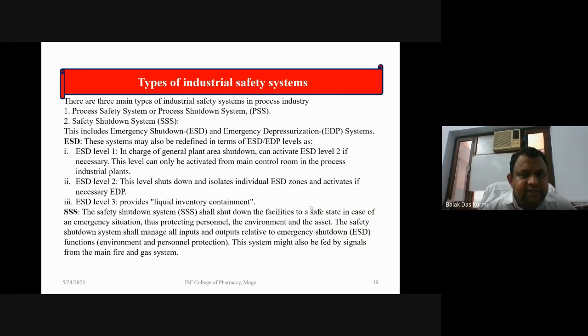Emergency shutdown systems may also be defined in terms of ESD levels. ESD level 1, in charge of general plant area shutdown, can activate ESD level 2 in the process industrial plant. ESD level 2 isolates individual ESD zones and activates, if necessary, the EDP. ESD level 3 provides liquid inventory containment.